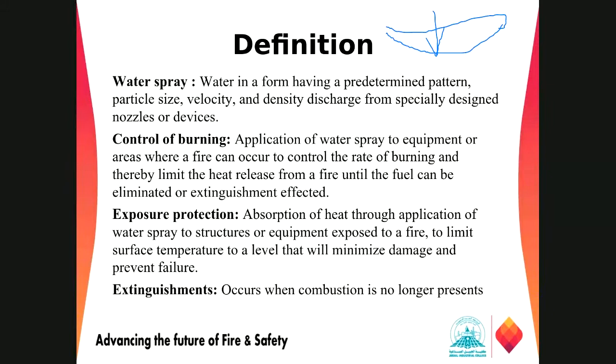So for control of burning, we have the application of water spray to equipment or areas where a fire can occur, to control the rate of burning. So we are only controlling the rate of the fire. We are not going for complete extinguishment, right? We are just limiting the heat release rate from a fire until the fuel can be eliminated or an extinguishment effect occurs. So this is the control of burning, where we are only controlling the fire.